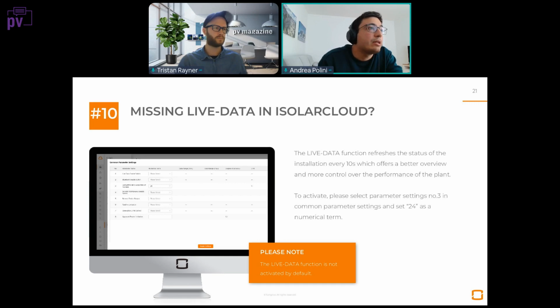And the number 3 is the duration of the live data per day. So how many hours would you like to receive live data from the device when it is accessed? If it is turned to 24, it means that the inverter will work in live data mode for 24 hours per day. And this is quite good for people that have a broadband connection or unlimited data connection, and they can handle streaming all the data from the inverter to the iSolar Cloud the whole day.